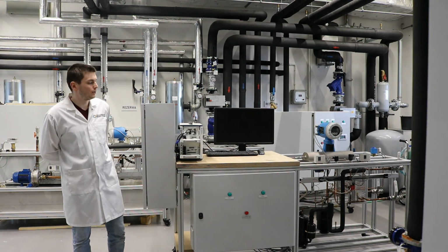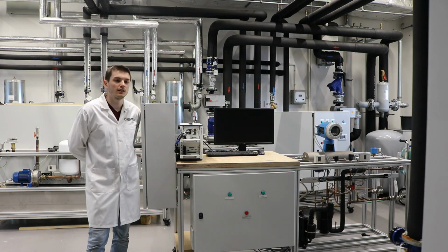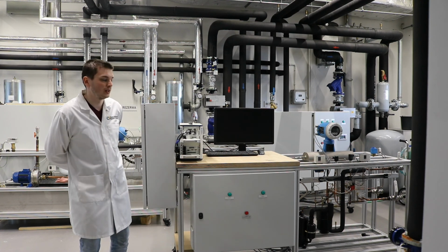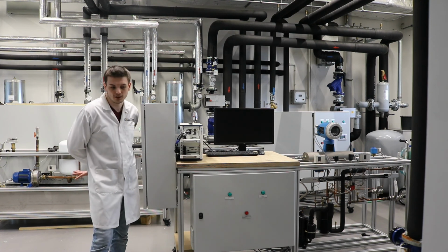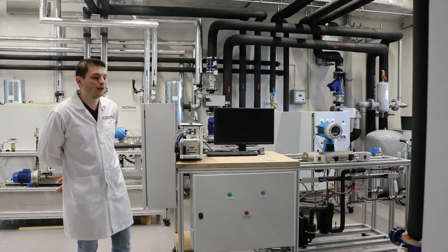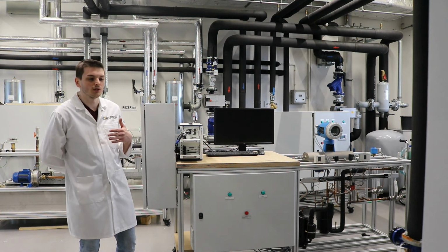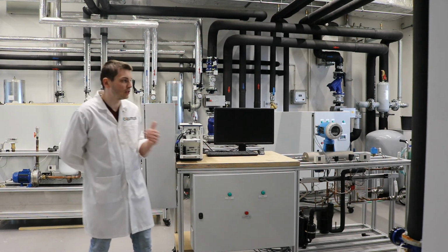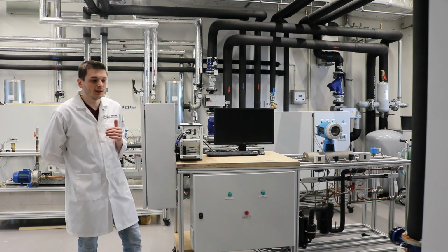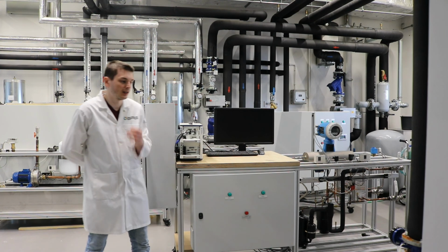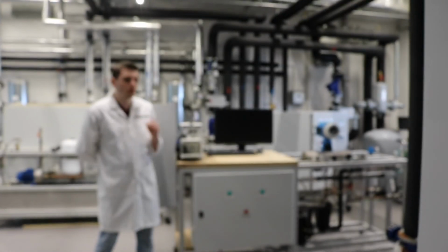As you already know, to make a characteristic of a heat pump, we need to take several measurements at different temperature levels, such as we did with the Mayekawa heat pump at different upper source return temperatures. But to be precise and do this correctly, we need to maintain a set temperature for a period of time.